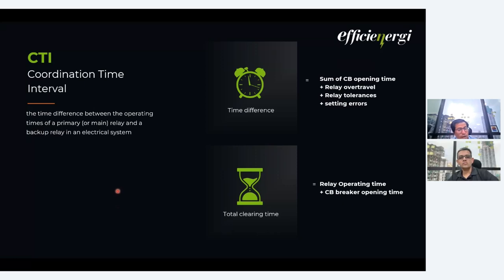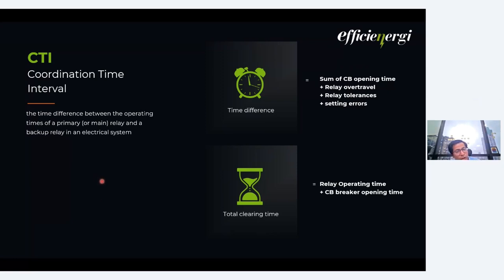But still, this relay will pick up. So whatever extra time is required for this relay, that is basically the overshoot time. It is there with every relay. So even if the downstream breaker or downstream system is isolating the fault, it is possible that the upstream breaker will trip, because it is not getting the proper resetting time. So that is possible, and we have to consider the relay over travel time as well.